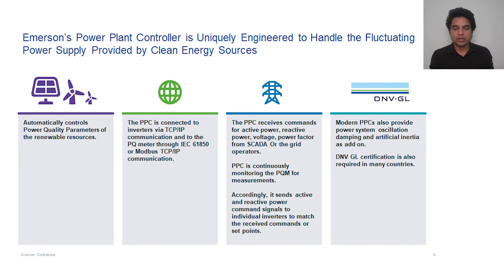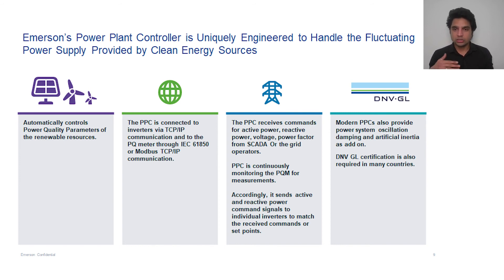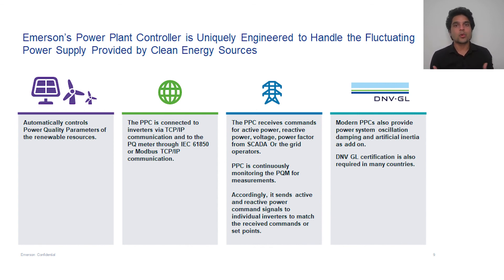Modern PPCs nowadays have two important parameters: power system oscillation damping and artificial inertia. A power system oscillation damping module should be present in the PPC to damp power oscillations. Because PV-based or wind-based generation does not have rotational inertia, artificial inertia should be implemented in the PPC. In many countries, PPCs may be required to have certification, and DNVGL is one of the bodies which provides that certification.